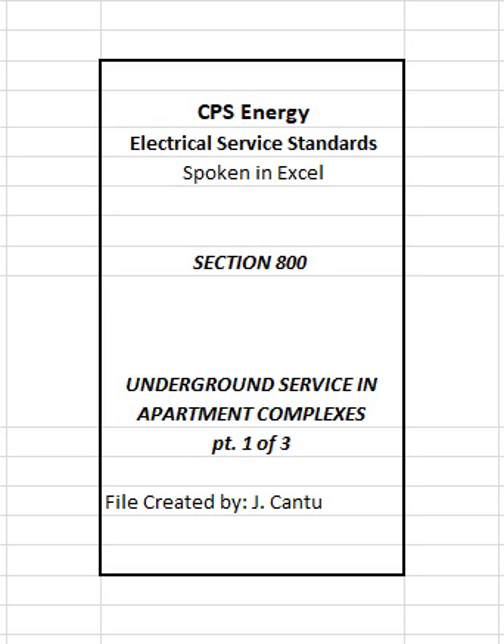2. Pad mount single-phase transformers and associated pads, transformers and pads to be furnished and installed by CPS Energy. Only single-phase, 3-wire, 120/240 volt service will be supplied for apartment services. Refer to Article 803. Exception: with prior CPS Energy approval, customer may elect to construct transformer pads. Customer shall coordinate with the CPS Energy Customer Service Representative to have all necessary inspections before covering or pouring.